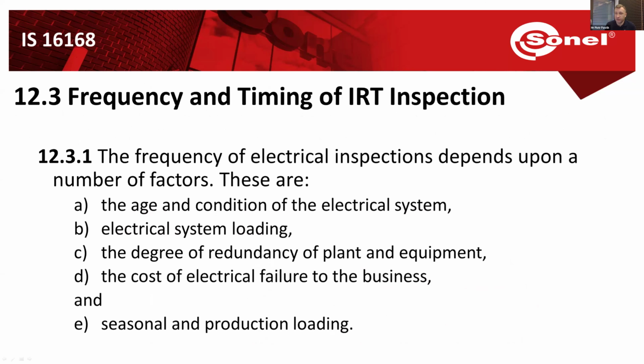Now, how frequently should we inspect the objects? There are several factors to consider: the age and condition of the system, the loading, the degree of redundancy of the plant and equipment, the seasonal or production loading, and the cost of electrical failures to the business. For example, an older system with high loads is more prone to overheating and breaking down.